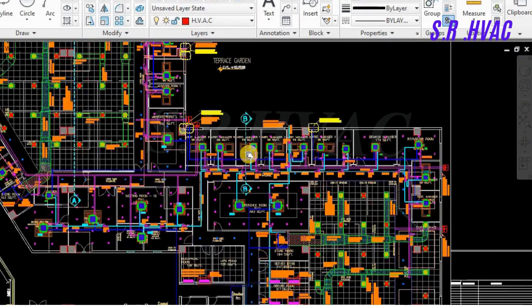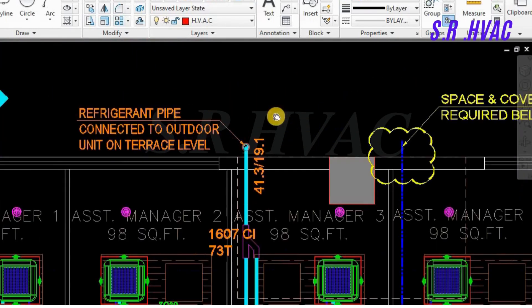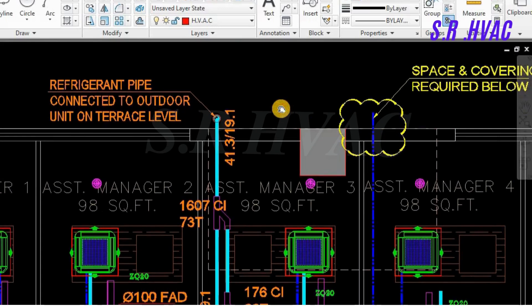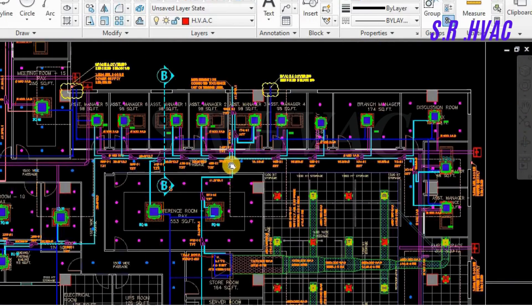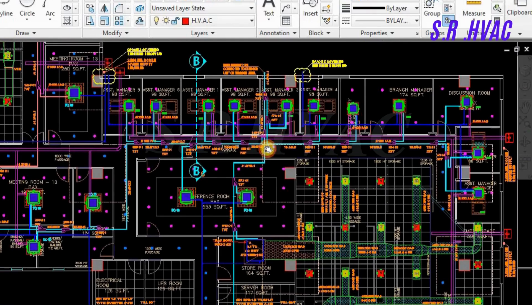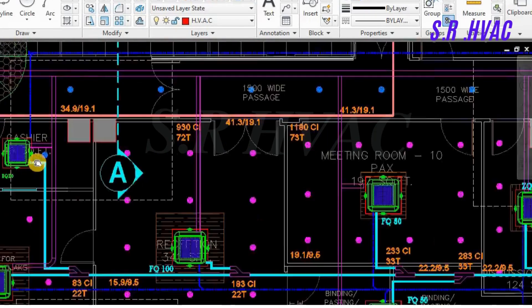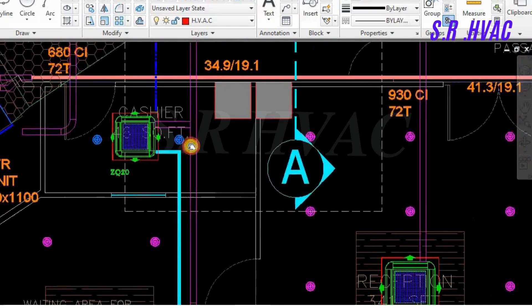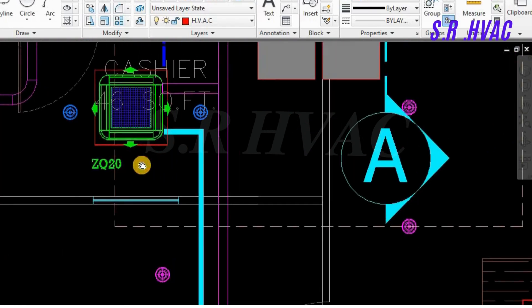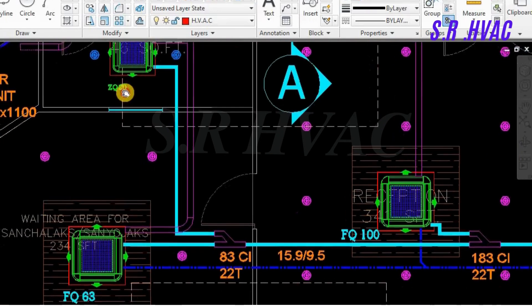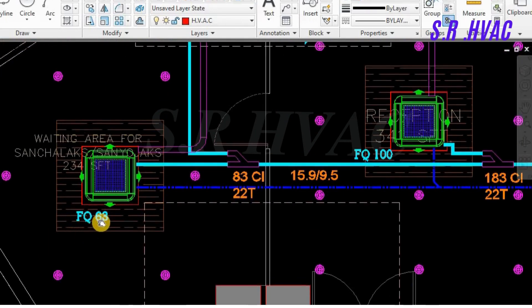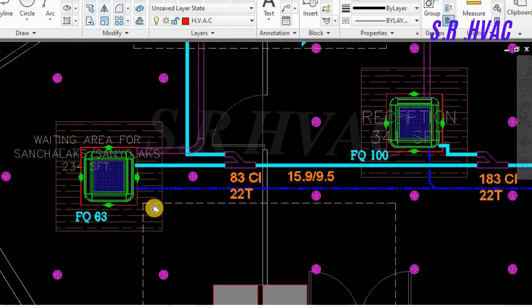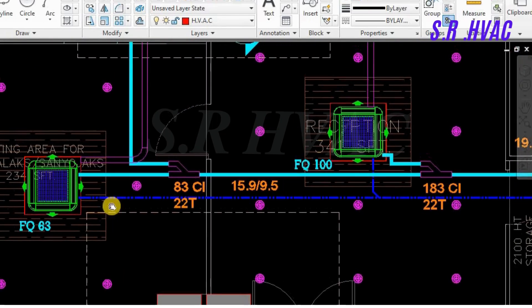First we will see the VRV from where it is. We will see from the outdoor unit the refnet pipe connected to the outdoor unit in the terrace level. So the outdoor unit is located on the terrace level. You can see the pipe size 41.3 and 19.1. So we will see from the start, from where it is starting from here. The last one is you can see in the cashier counter it is ZQ. This means this is 0.6 TR and it is 2 by 2 unit. It is the code for Daikin. This is the FQ63, this means it is 2 TR four-way cassette unit. You can see it is located in the wait area.